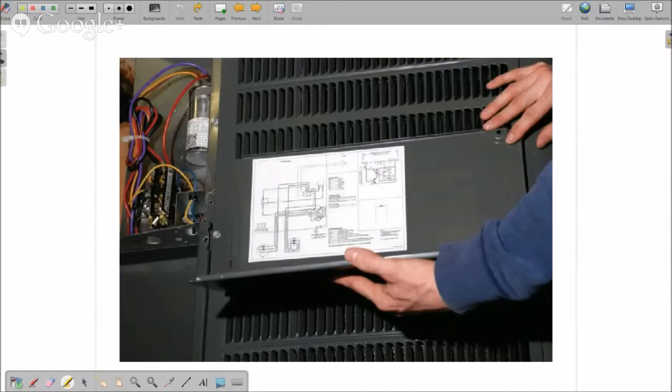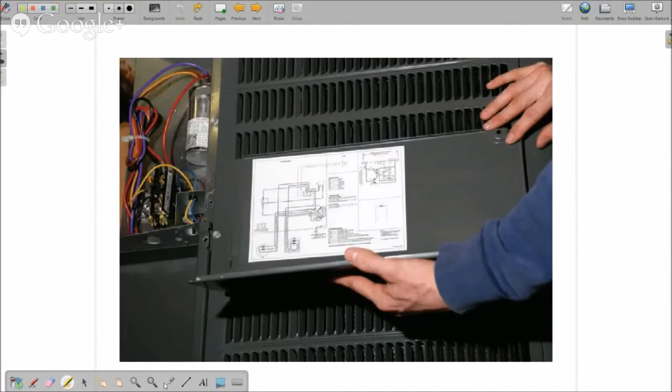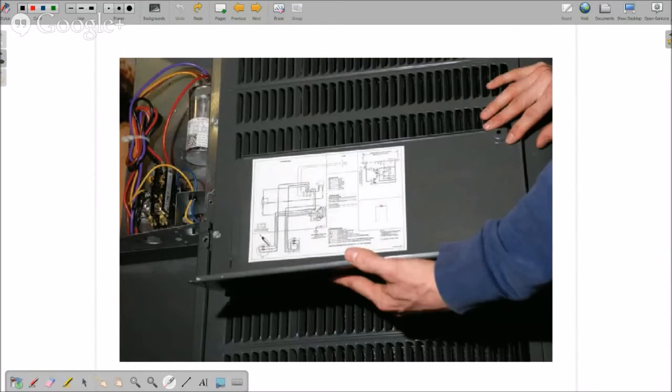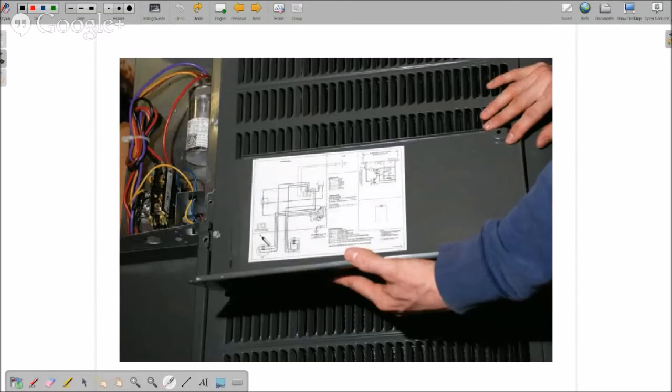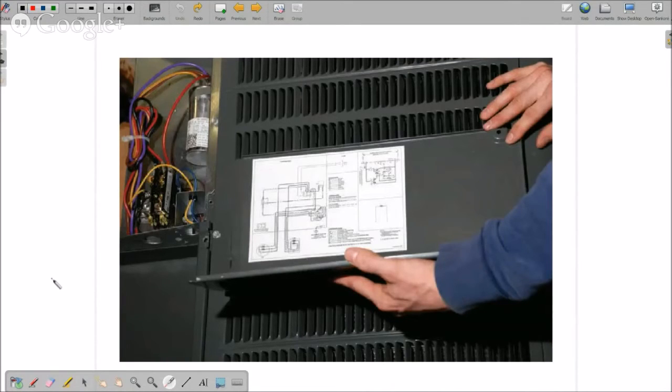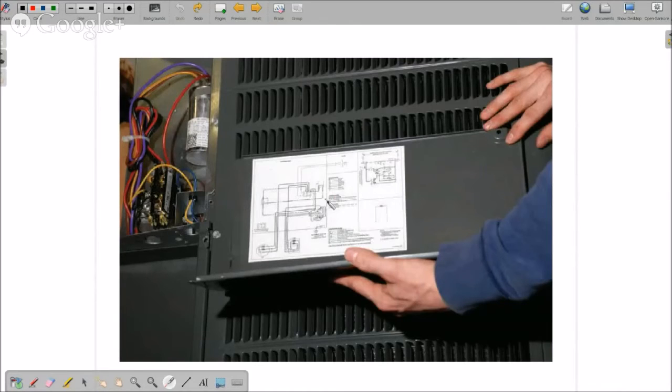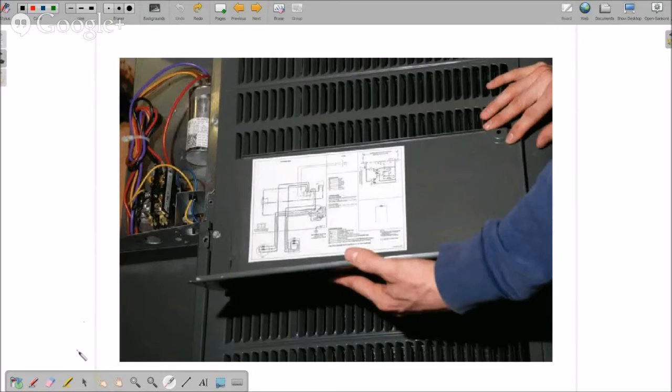So if it's the outdoor unit, you take the cover off to the electrical panel over here, it will have some type of schematic diagram, and the same with the indoor unit. And if you're lucky, Trane sometimes has service facts which has even more information for you. And if you're unlucky, then this will be completely destroyed and you're going to have to rely on chasing wires to do it.